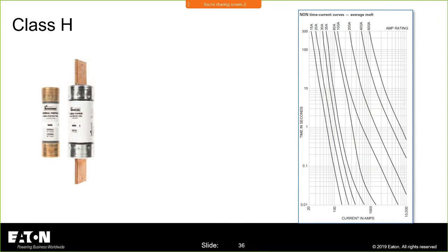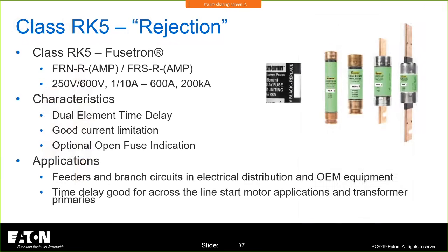The trip curves, I plotted that trip curve. Look how they slope off to the right. They're way out there on the right. It takes a lot of current to get these puppies to go because I told you how they're constructed. They're not constructed like those other fuses. These are the ones you want to get into. You want to get into your current limiting dual element time delay fuses. Your class T's, they're built to reduce incident energy. They're built to protect, not the class H's.